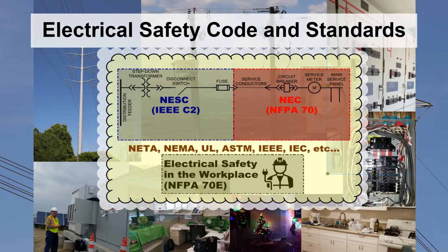To clarify, think of electrical code broken up by the equipment being installed. NESC and IEEE C2 cover everything on the utility side, refineries, or high voltage—distribution feeders, step-down transformers, disconnect switches, fuses. The utility typically owns everything up to the meter, and that class of equipment is outlined in the NESC, with some overlap with the NEC on installing residential, lower-voltage equipment.